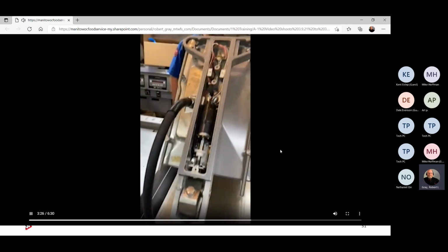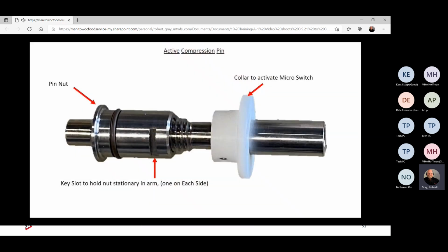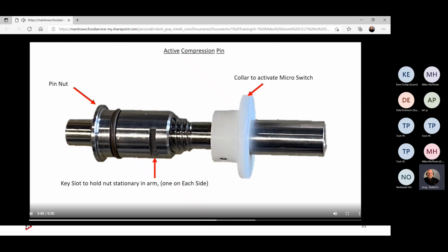Inside the arm, you're going to find the active compression motor, the compression pin assembly, some wiring, and a micro switch. Let's take a moment and look at the active compression pin. You can see here you have your pin nut with the key slot to hold the nut stationary inside the back of the arm. There's a slot on each side. Then you can notice the threads, and then the solid pin housing that goes through it. Then you have a collar to activate the micro switch, with a set screw so it doesn't move up and down the shaft.